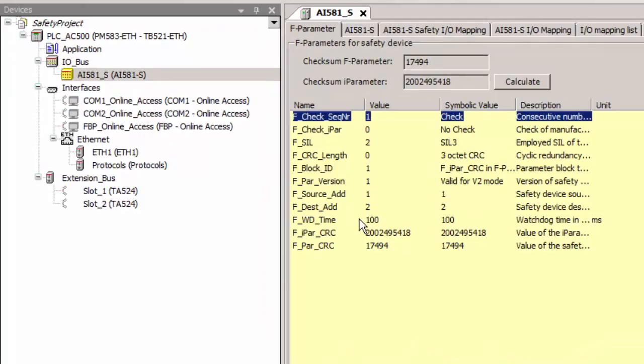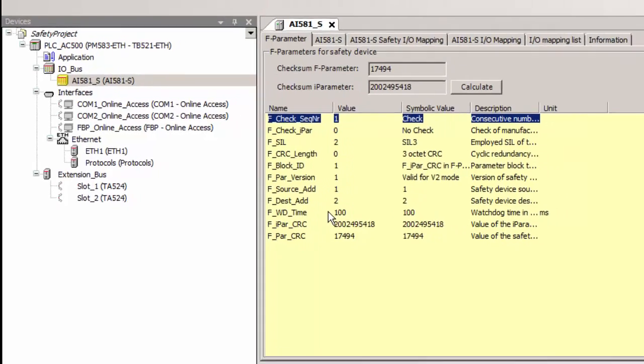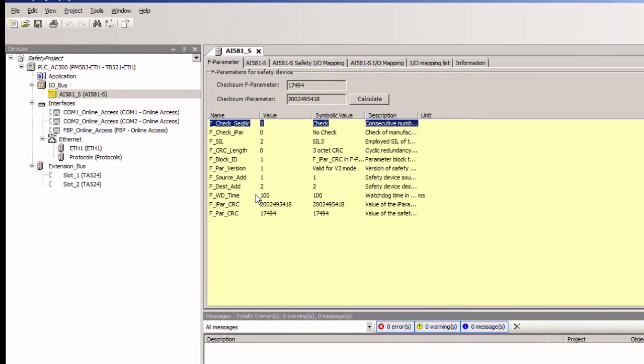One of the major parameters to be set is F destination address and this value needs to match with the rotary switches setting on the module. For this case we need to set it to 2 as per the actual hardware setting and hence the default setting is good enough.